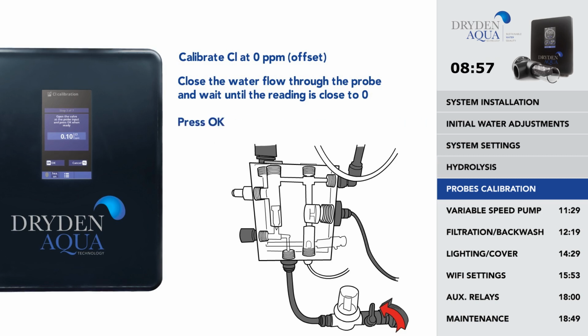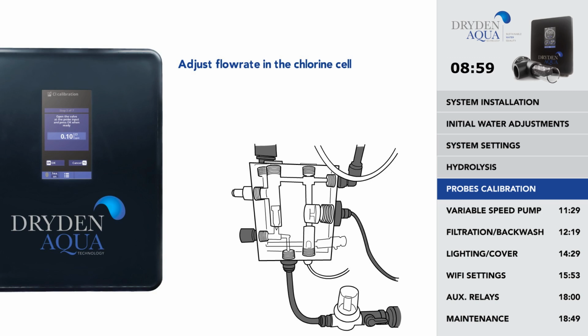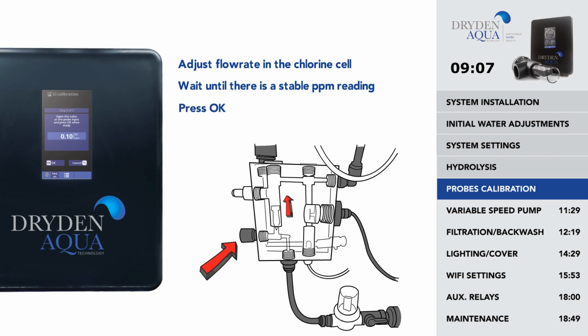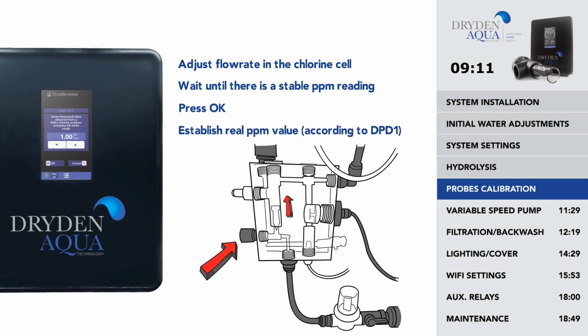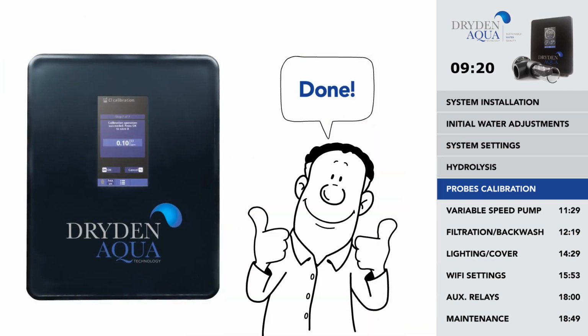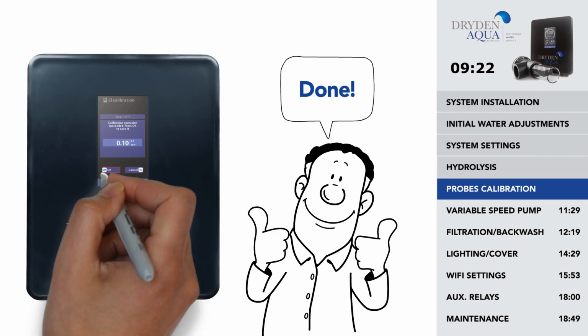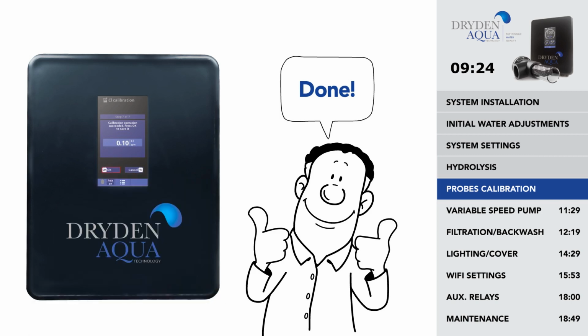Then, set the water flow to the correct rate of 80 to 100 liters per hour. Wait for 1 to 10 minutes until there is a stable ppm reading and press OK. Finally, establish the real ppm value with the up-down keys according to your DPD1 value and press OK. You are done. Press OK to save calibration. If this screen is not shown, repeat the calibration process.